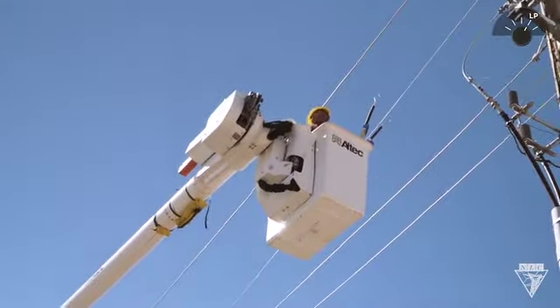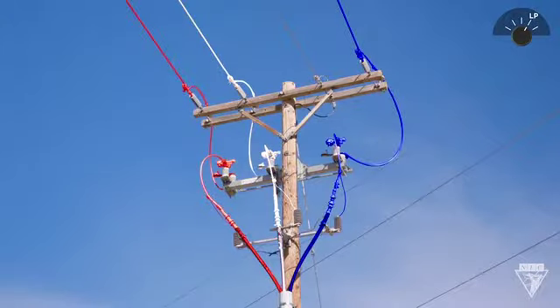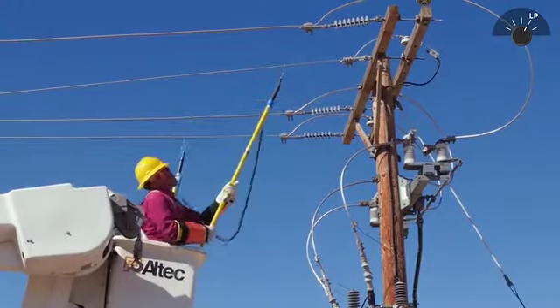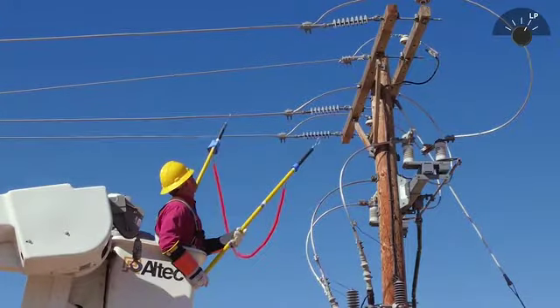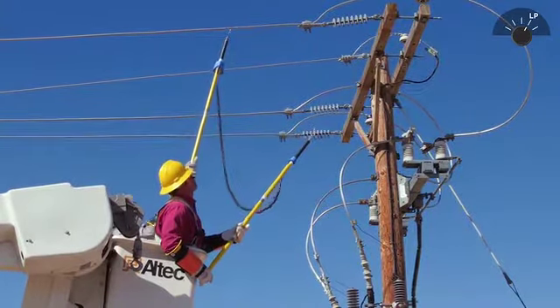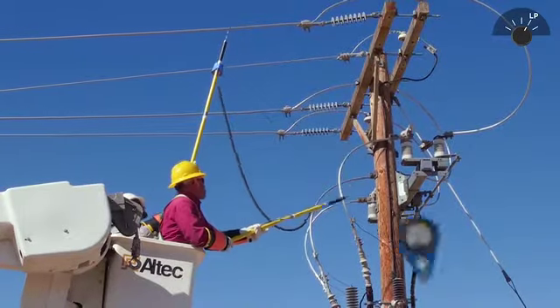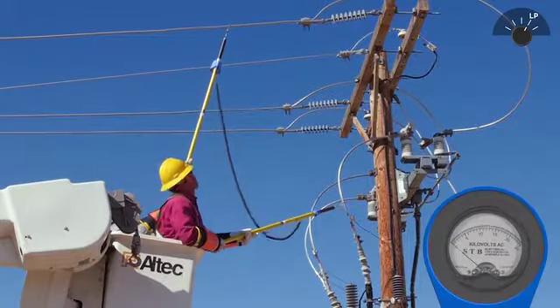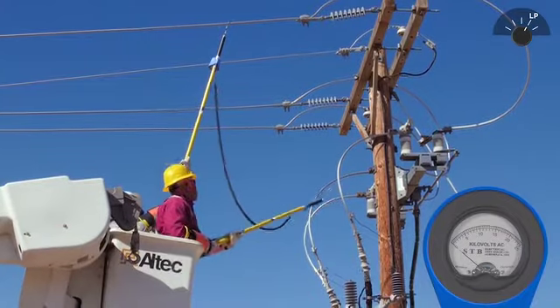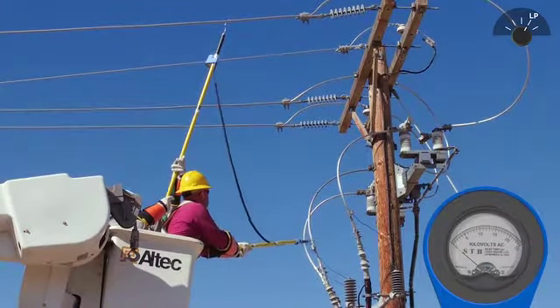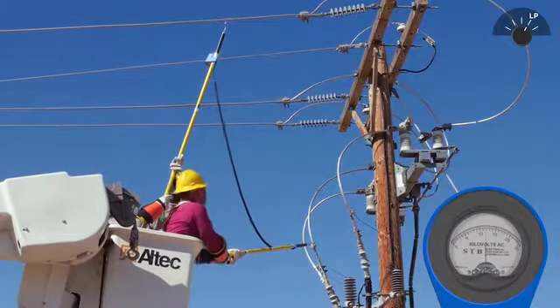On this 12 kV line, we'll confirm proper phase sequence between the open points of the same phase. When approaching the line, always stay clear of the insulated jumper connecting the meter and phasing probes. If the meter reads 0, the phases are in sequence or the meter is malfunctioning. To make sure it's not malfunctioning, perform a cross-phase check after any 0 reading.